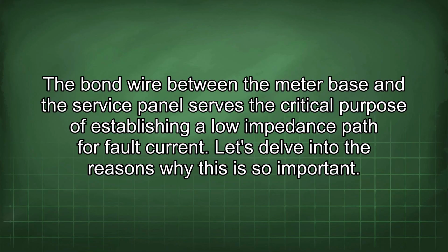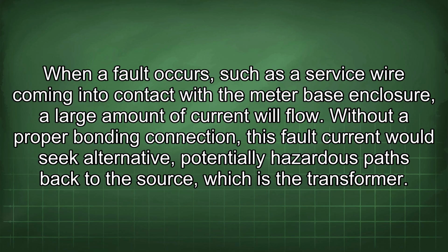The bond wire between the meter base and the service panel serves the critical purpose of establishing a low impedance path for fault current. Let's delve into the reasons why this is so important. When a fault occurs, such as a service wire coming into contact with the meter base enclosure, a large amount of current will flow. Without a proper bonding connection, this fault current would seek alternative, potentially hazardous paths back to the source, which is the transformer.